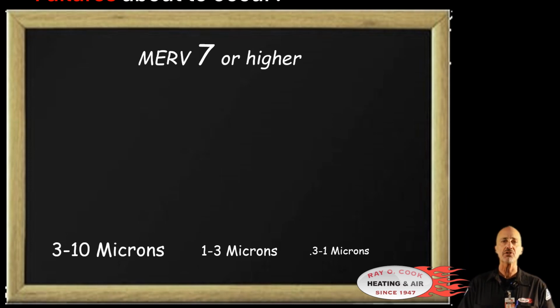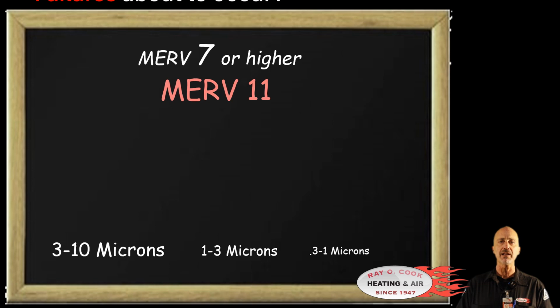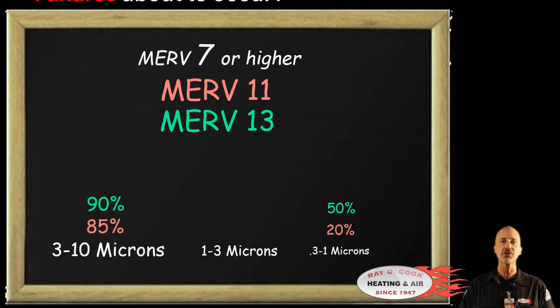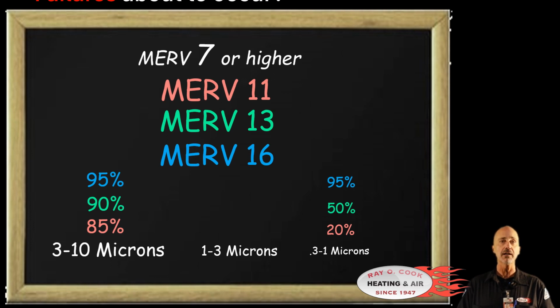Most modern air filters start about MERV 7 or higher. For example, a MERV 11 rated filter will capture about 85% of particles between 3 to 10 microns. As the particles get smaller, the filter captures less. It will only capture about 20% of particles sized at 0.3 microns to 1 micron. A MERV 13 filter will capture more particles at a smaller size, and a MERV 16 does even better. So why not just install a MERV 16 filter and call it good? This is where things can go bad quickly.